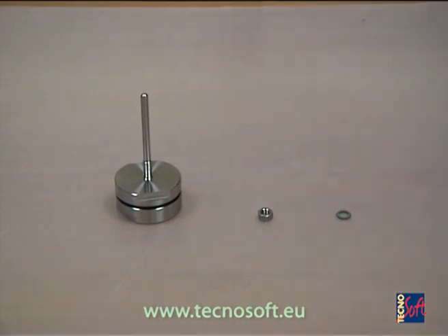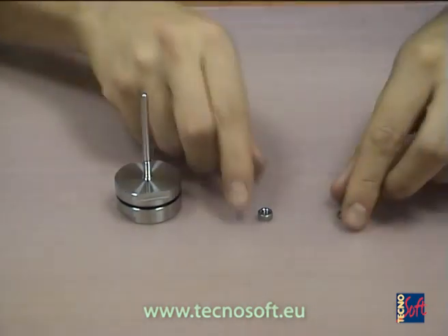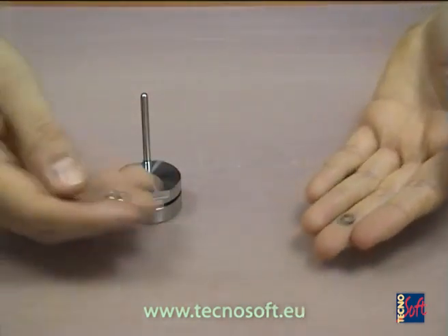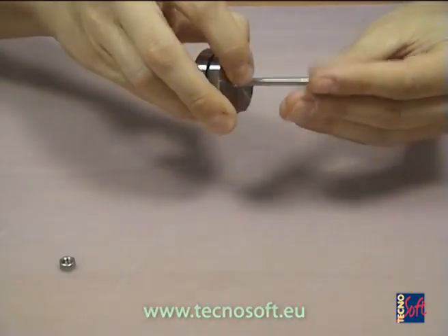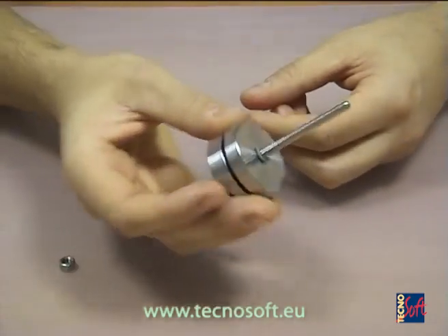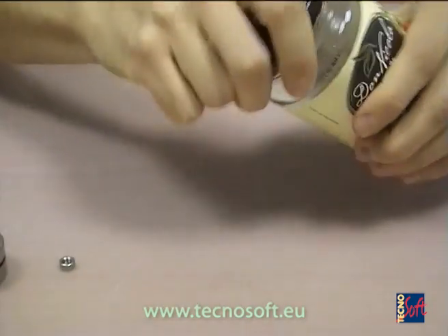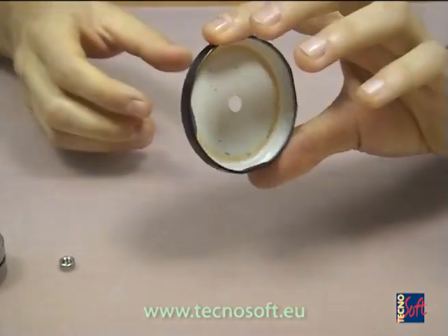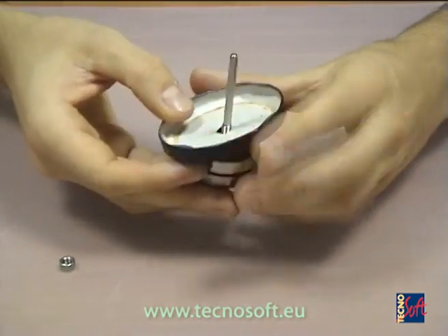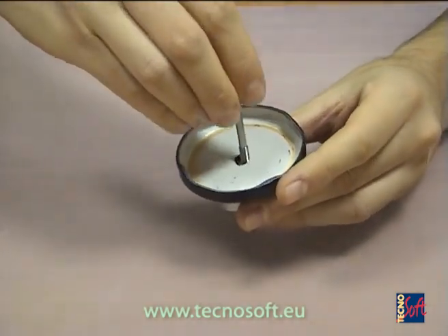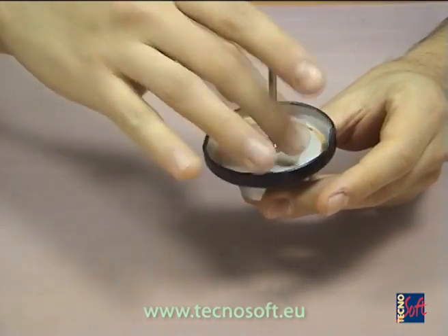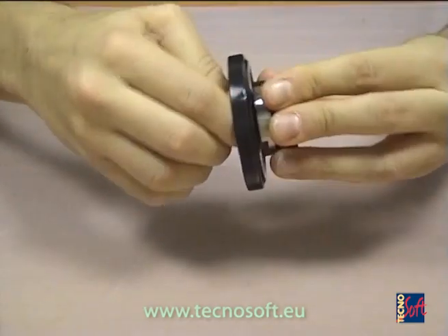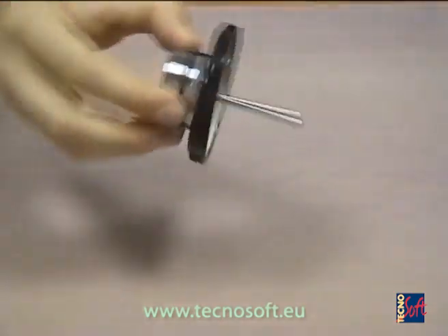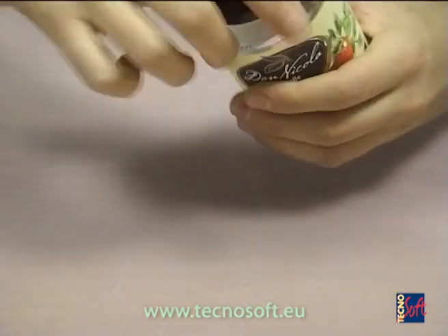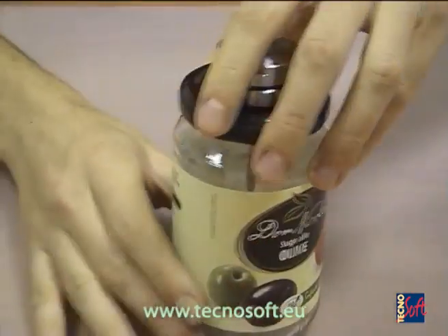If we have an open container where we can act both on the inside and the outside, like the cap of a jar, we can use a threaded probe and a counterbolt to fix the logger to the surface. We put an O-ring on the threaded part of the probe. We take the cap and, of course, we put the probe in the hole. And then we screw the counterbolt to fix it to the cap. Of course, this solution implies that the length of the probe is exact and correct to reach the cold spot inside the container.